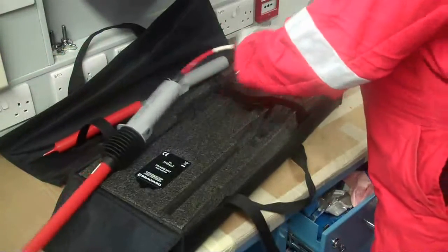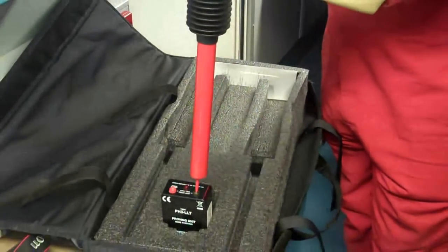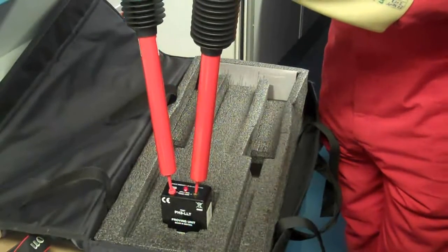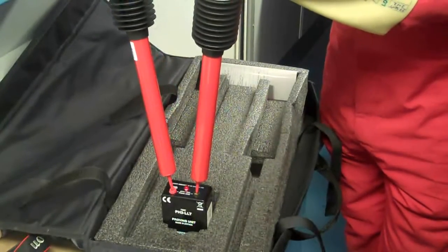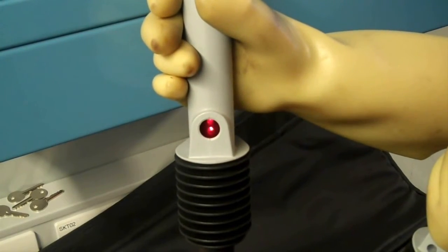The probes are now proved using a dedicated proving unit. The proving unit contains its own self-test function in the form of a light which glows when it is operated correctly. The light on the probe should also glow during this test to confirm satisfactory operation.